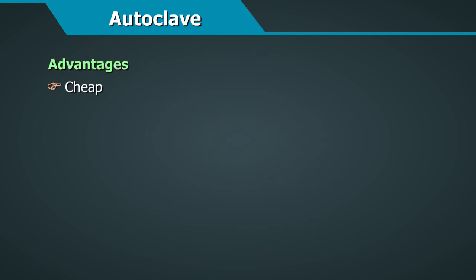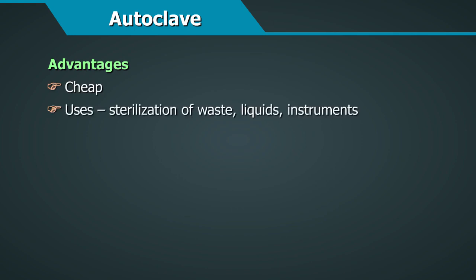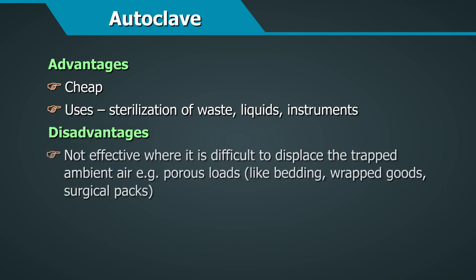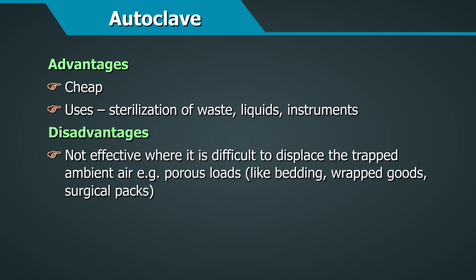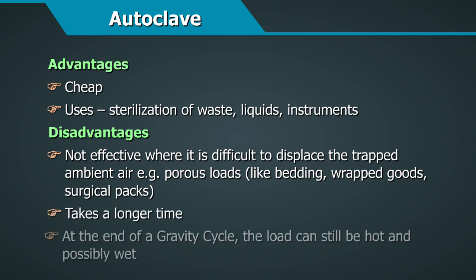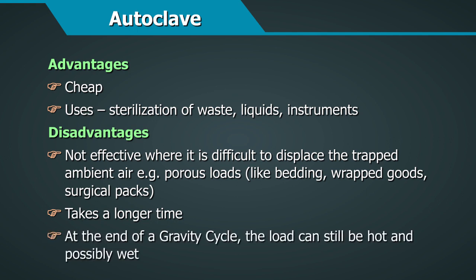Advantages: this is a cheap method. Uses: for the sterilization of waste, liquids, and instruments. Disadvantages: this method is not effective where it is difficult to displace the trapped ambient air. For example, porous loads like bedding, wrapped goods, surgical packs. It takes a longer time, and at the end of a gravity cycle, the load can still be hot and possibly wet.